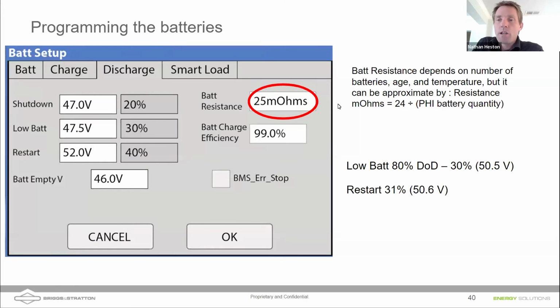Mike asks, what about overcurrent protection? Is this required on and off common DC bus bars when multiple inverters are used? Correct. And yeah, the answer is overcurrent protection. If you're using a combiner, there is overcurrent protection built into the Sol-Ark 15K. You've got 200 amp breakers there. But if you're doing large banks of batteries and a combiner, like a 1,000 amp Midnight combiner, you would want to have overcurrent protection on each of those battery cables.